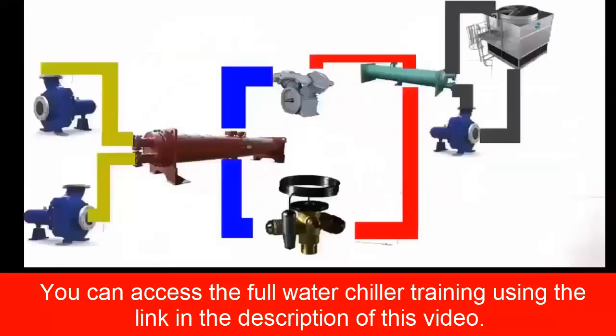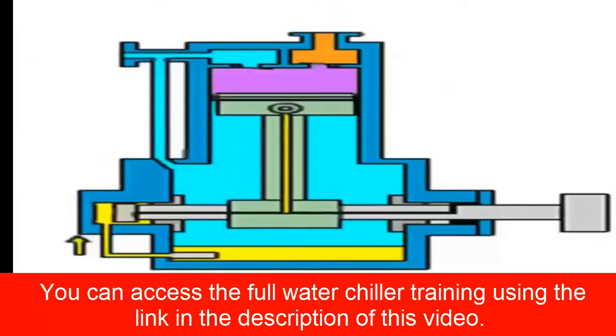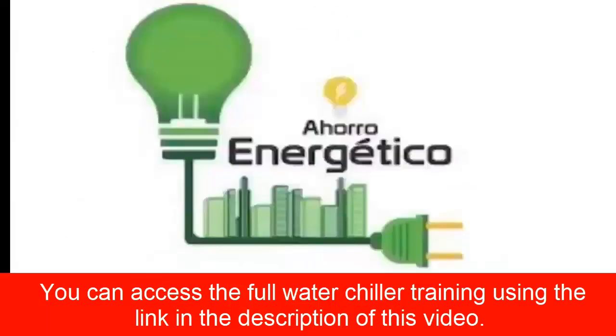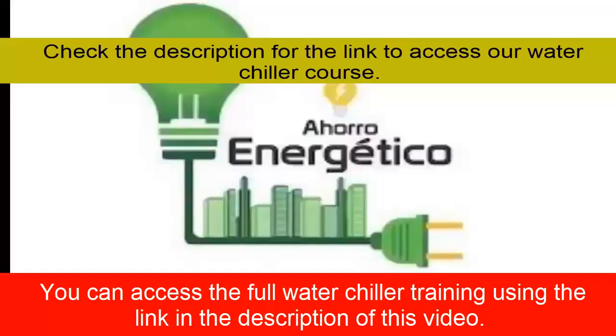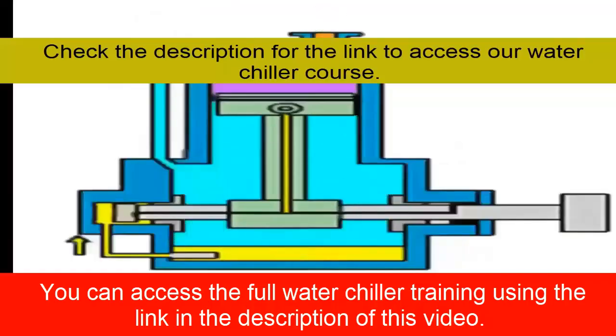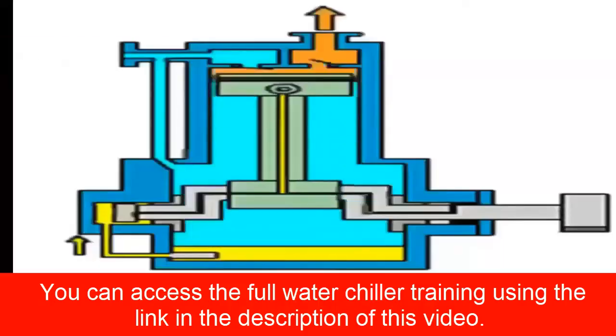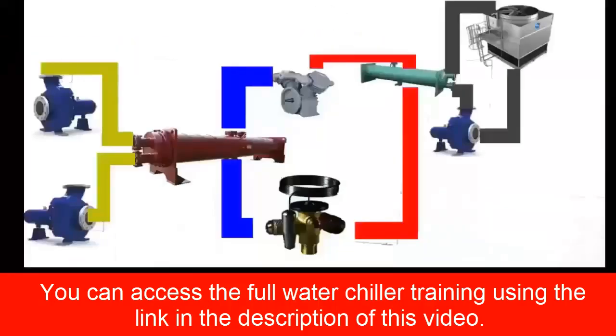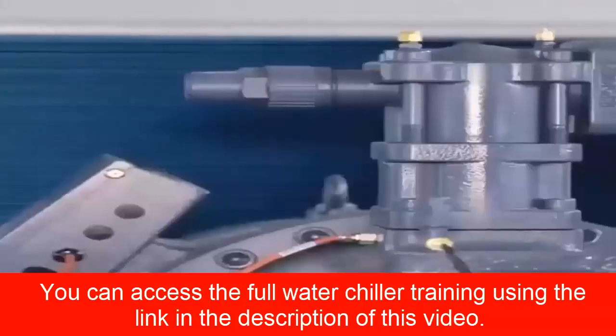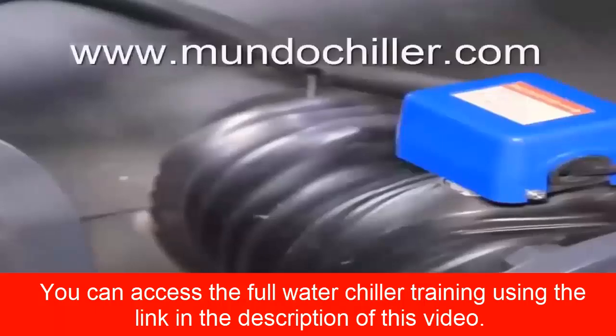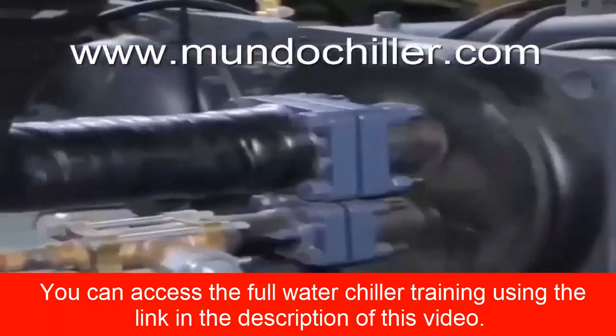Advantages of a water-cooled chiller. The main advantage is that it makes heat removal at the condenser easier. This results in lower condensing pressures, less compressor workload, lower electrical consumption, higher energy efficiency, and better coefficient of performance, or COP. Since the compressor is typically the component that consumes the most energy, any reduction in its load has a positive impact on the total plant consumption. Although there is water consumption due to evaporation, this disadvantage is compensated by the overall energy savings of the system.